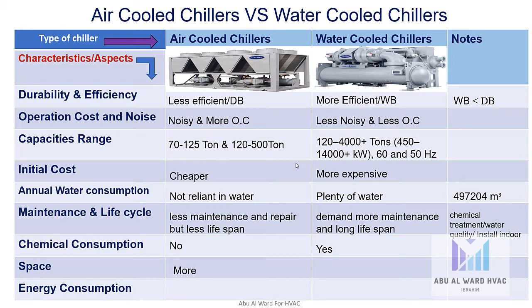Space requirement for air-cooled is more because it's bigger than the water-cooled chiller, and it is less for water-cooled. Energy consumption requirement for air-cooled is more. It requires around 1.25 kilowatt per ton, while it is less for the water-cooled, around 0.55 to 0.8 kilowatt per ton.